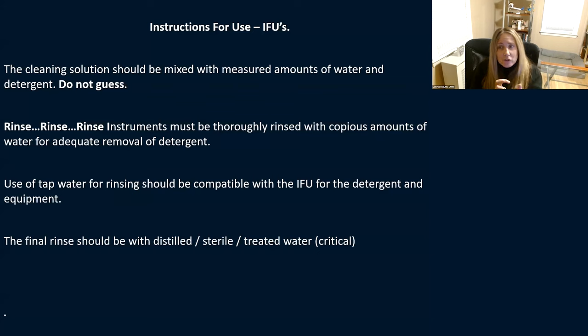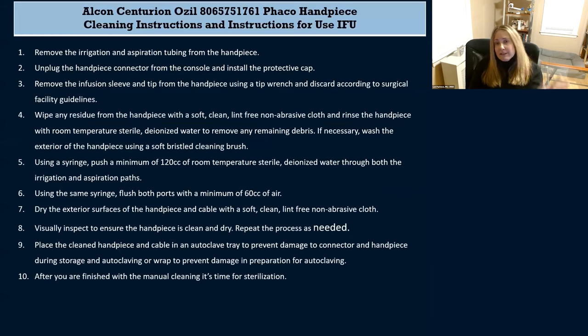If you're using tap water, please be sure the instructions for use say you can. No matter what, the final rinse really should be done with distilled, sterile, or treated water. Here's an example from a phaco handpiece IFU — it says: push a minimum of 120 cc's of room temperature sterile deionized water through both the irrigation and aspiration paths, then flush both ports with a minimum of 60 cc's of air. This is the company telling you what you need to do to properly clean the instrument.